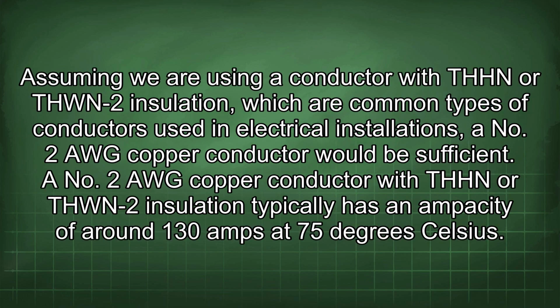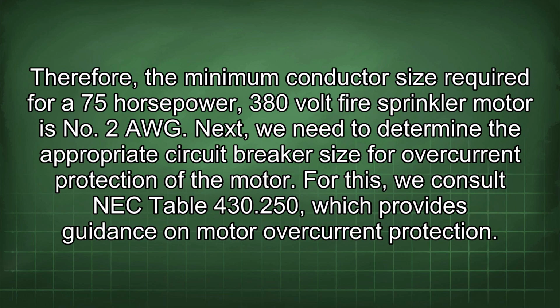Assuming we are using a conductor with THHN or THWN-2 insulation, which are common types of conductors used in electrical installations, a No. 2 AWG copper conductor would be sufficient. A No. 2 AWG copper conductor with THHN or THWN-2 insulation typically has an ampacity of around 130 amps at 75 degrees Celsius. Therefore, the minimum conductor size required for a 75 horsepower, 380 volt fire sprinkler motor is No. 2 AWG. Next, we need to determine the appropriate circuit breaker size for overcurrent protection of the motor.